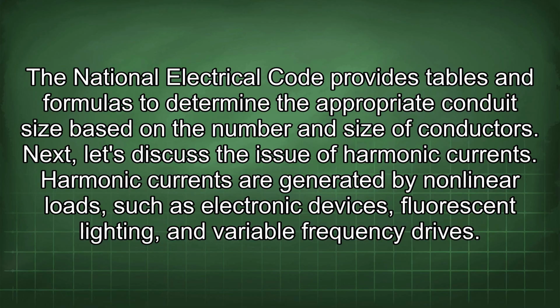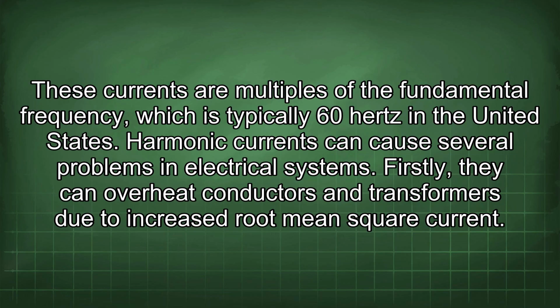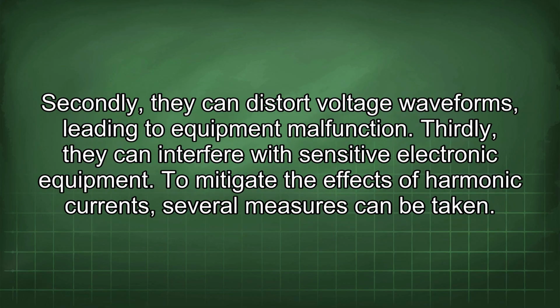Harmonic currents are generated by nonlinear loads such as electronic devices, fluorescent lighting, and variable frequency drives. These currents are multiples of the fundamental frequency, which is typically 60 Hz in the United States. Harmonic currents can cause several problems in electrical systems. Firstly, they can overheat conductors and transformers due to increased root mean square current. Secondly, they can distort voltage waveforms, leading to equipment malfunction. Thirdly, they can interfere with sensitive electronic equipment.